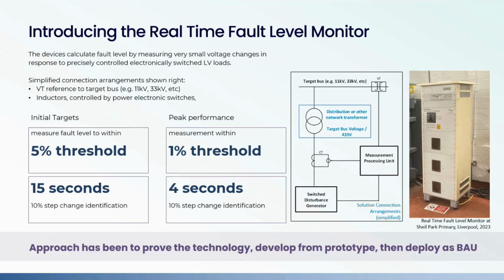The way we connect these up is, firstly, we need to connect the bank of inductors to an LV distribution supply or LV distribution board that has to be fed directly from the same target bus bar that we're looking to measure fault level at. In that example, the distribution transformer next to the RTFLM steps the voltage down from 6.3 kV to LV, and there's cables out the back of the RTFLM that run alongside and connect to that LV distribution board. We then take a voltage measurement from the voltage transformer on the target bus bar, which could be 6.3, 11 or 33 kV and so on.